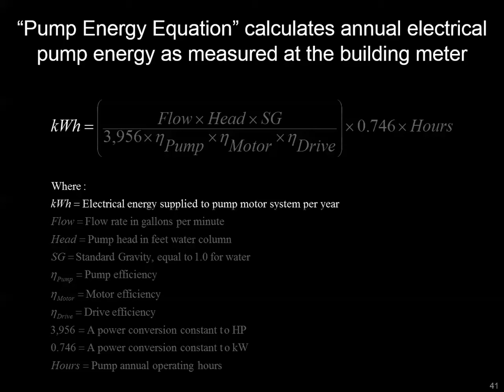It's important to realize that we can use this pump equation not just to look at the pumping system as a whole, but also for specific components. If we want to look at the energy associated with a very specific pressure drop — across some valve or set of piping — we can plug those numbers into this equation to understand the pump energy associated with those components.